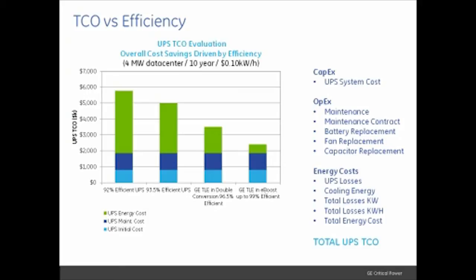Again, you can see the 92% UPS all the way down to the 96.5%, all of those in double conversion. The bar on the far right of the chart is what we call e-boost or eco mode. Some people now refer to it as multi-mode, where you operate the UPS in a high efficiency mode that gets up to 99% efficiency, with improved savings in that model as well.